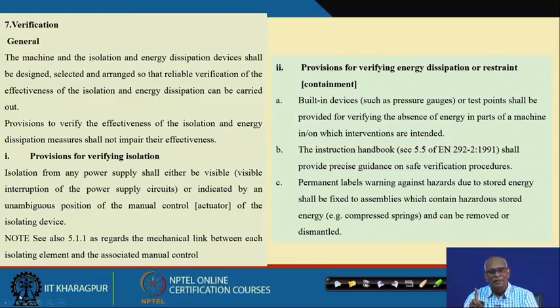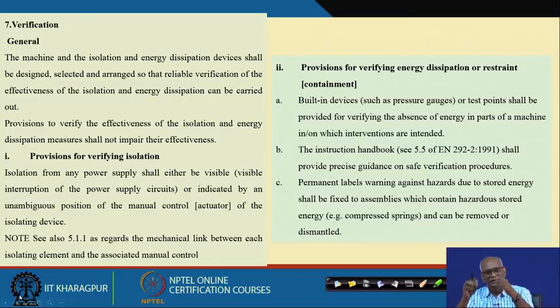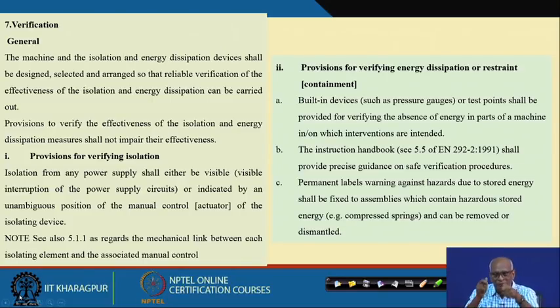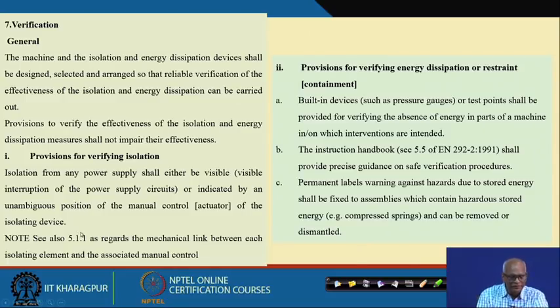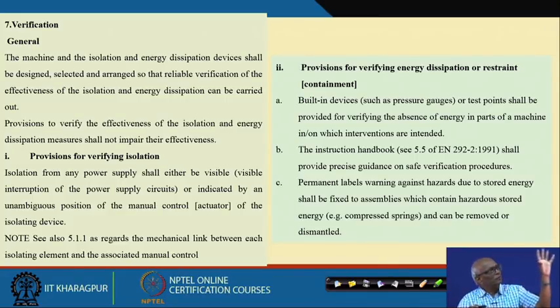Verification is very very important. Even if everybody says they have put off the power, separated it, put the locks and tags, it is essential to verify whether it is done properly at the final place where people are working. There are many ways of verification: visible verifications, built-in verification using pressure gauges — if the pressure gauge shows zero, there is no pressure. Instruction handbooks specify what to check. For electrical systems, you can use a tester or megger to see whether power is there or not. You have to verify with different means to ensure isolation is done.